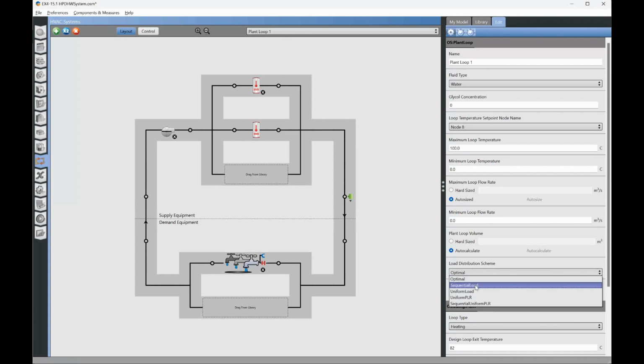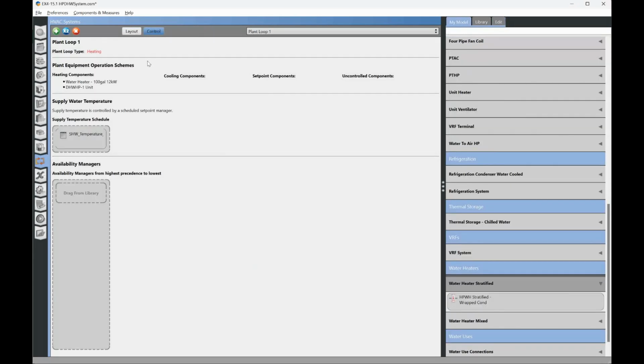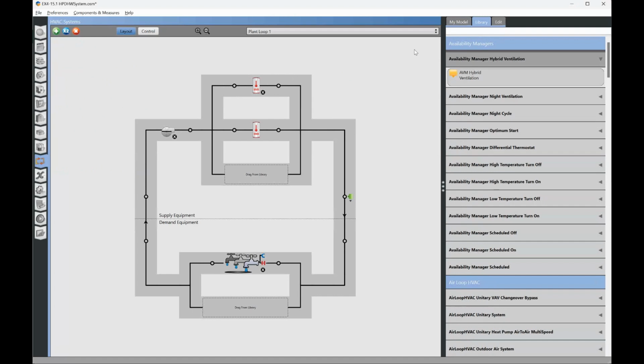Let us change this to a sequential load. So that means it loads up the first hot water heater first, and then if it needs more capacity, it turns on the second one. Unfortunately, our heat pump water heater is in second place at the moment. You can see that on our controls tab. You can see that the standard electric hot water heater is in first place. The heat pump is in second place. So it's going to prioritize this standard hot water heater. So we need to swap those two.